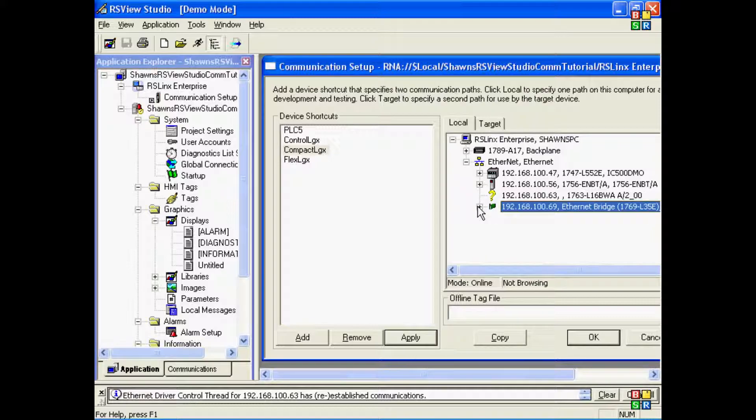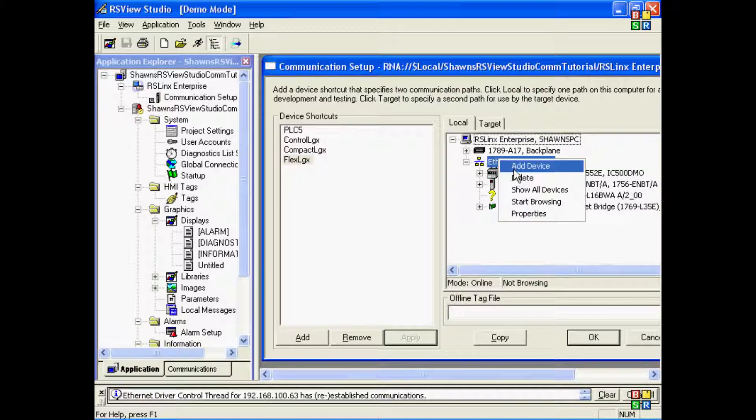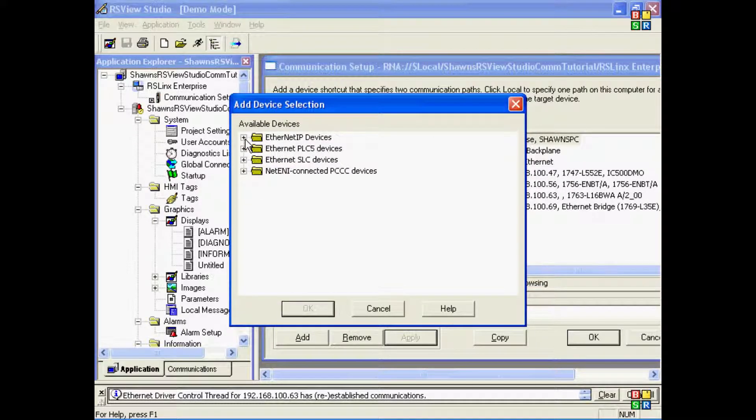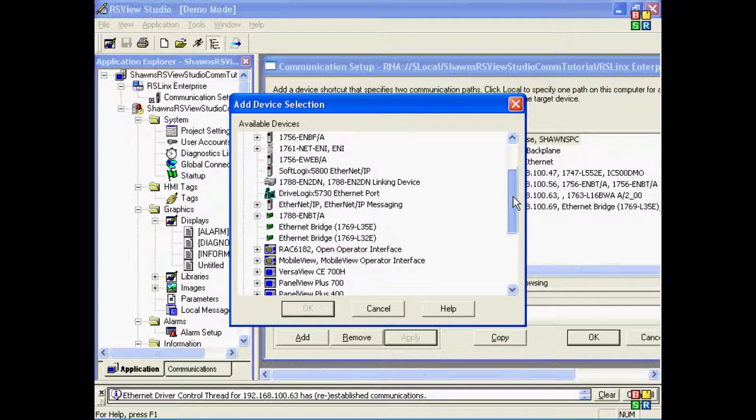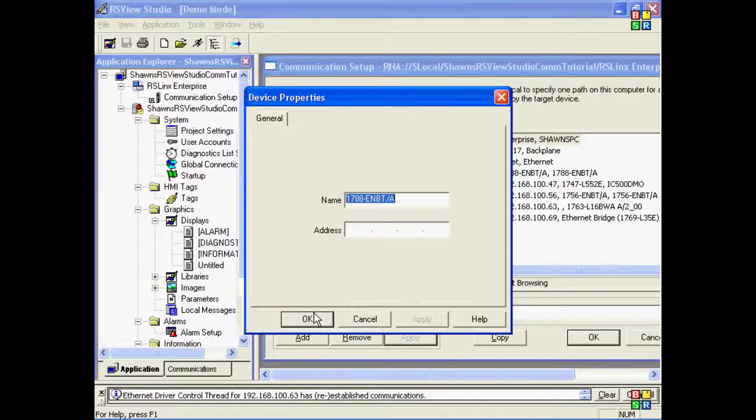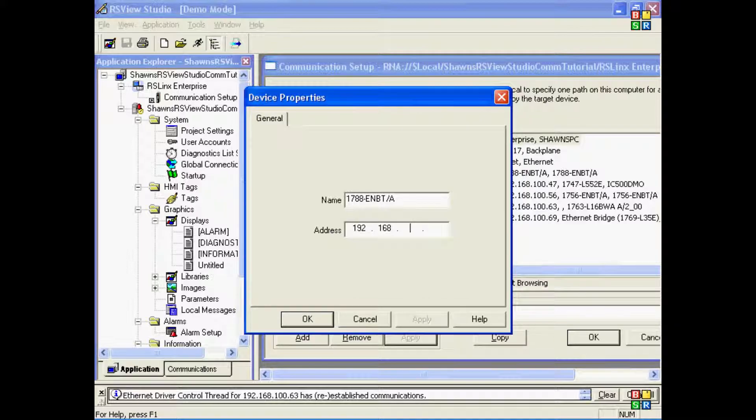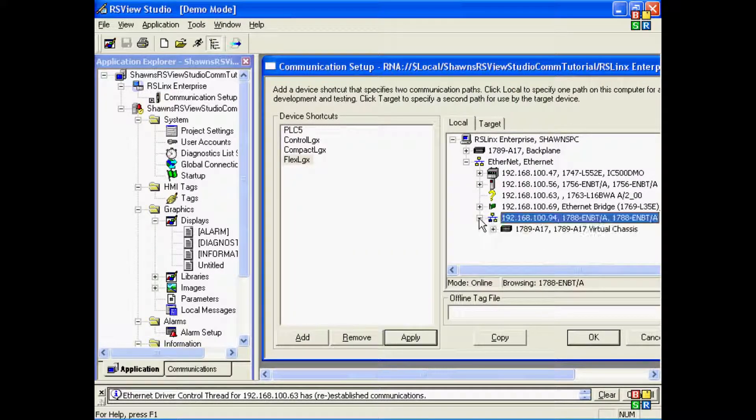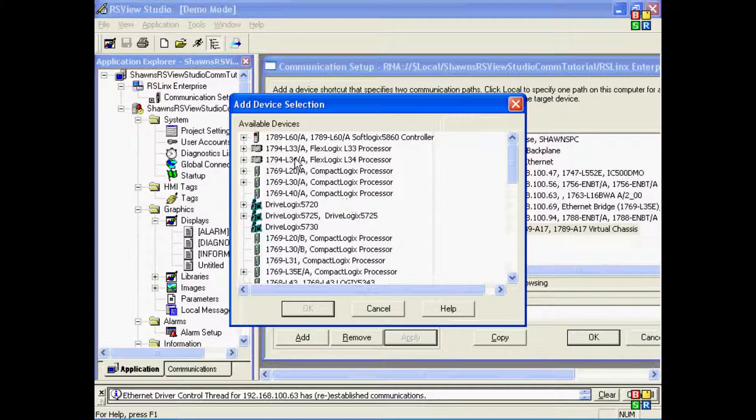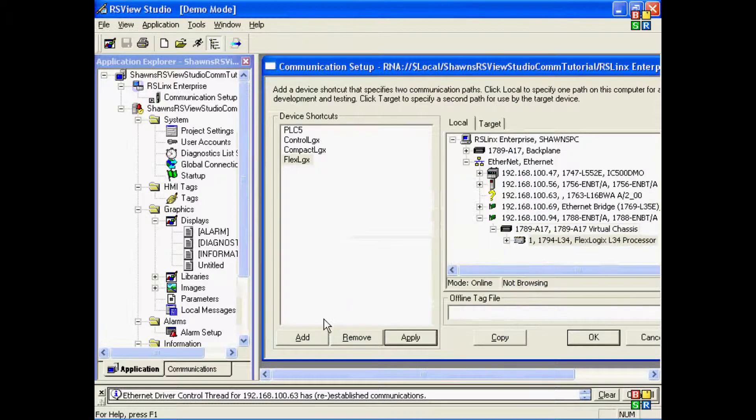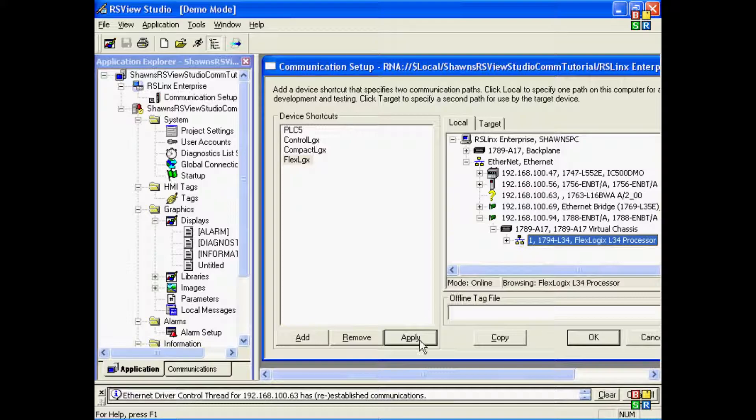Now on my last item, the FlexLogix, I actually don't have one on my network, so I'm going to go ahead and add this manually. I'll right-click Add Device. I'll go ahead and select my 1788 Ethernet card for the FlexLogix. Give it a valid address on my subnet. And then on the chassis, I'll add in the actual 1794 processor. And at this point, I'll select the FlexLogix shortcut, the processor, and press Apply.